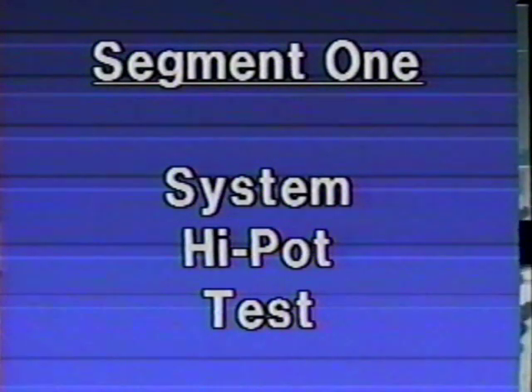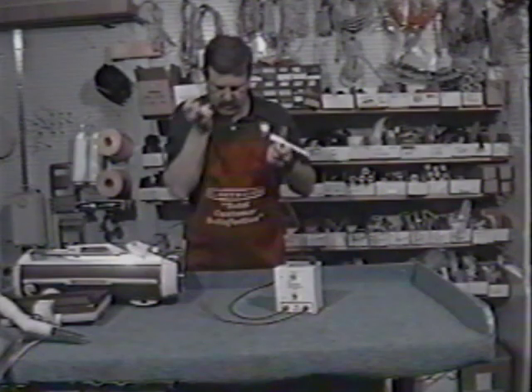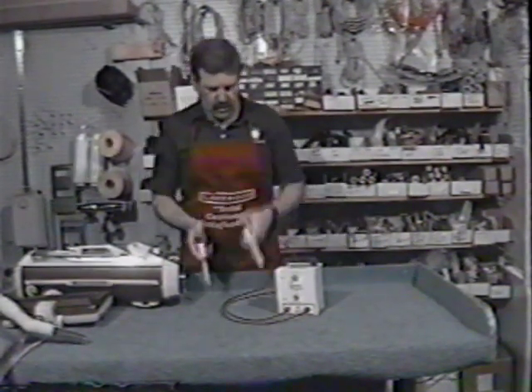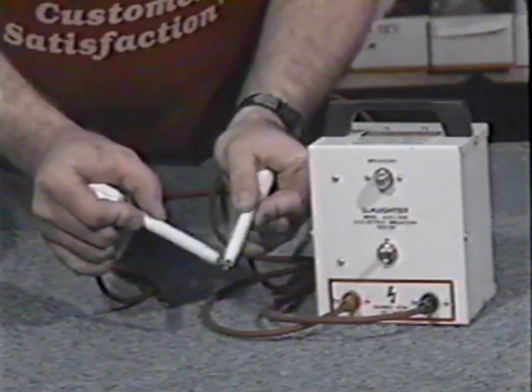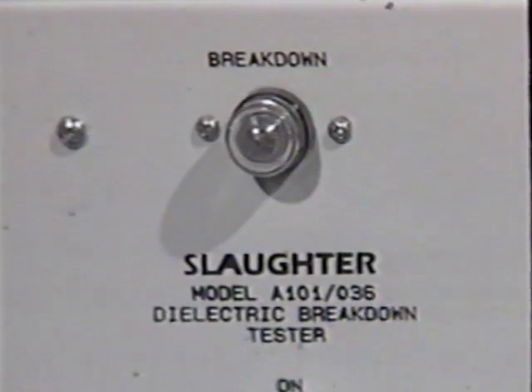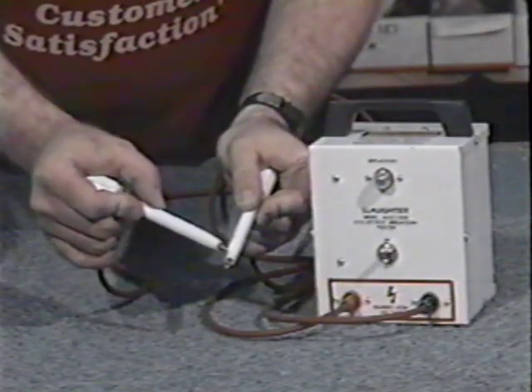We begin with a hi-pot test of the system to detect if any electrical problems exist. First, verify the tester is functioning properly by touching the probes together. The light should illuminate, signifying proper function. If not, the tester must be replaced.